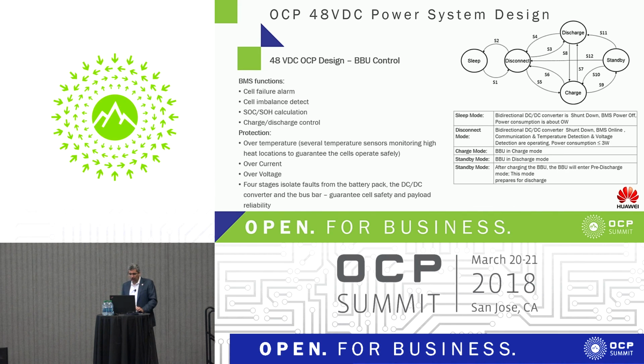Finally, let's talk about control. There's a lot of ways to do batteries. We picked basically what we consider the safest way to do this. We have both a battery management system and a DC-to-DC converter in each battery module. They're self-contained, they're independent, we're not depending on some controller someplace else telling the battery what to do. The batteries are managing themselves. The battery management system has temperature probes all over the place, they know the temperatures of the cells, and anything that goes out of range, they manage that.